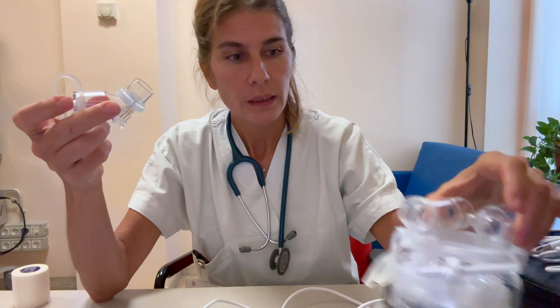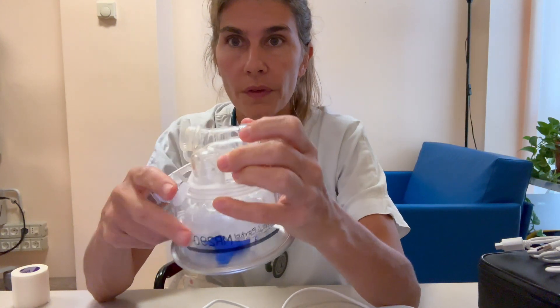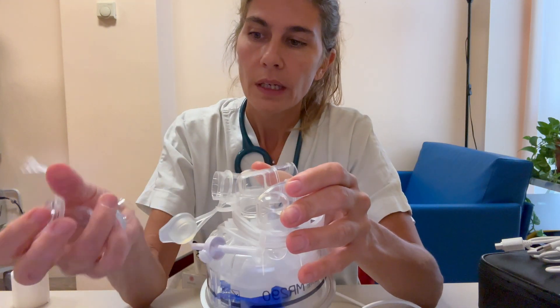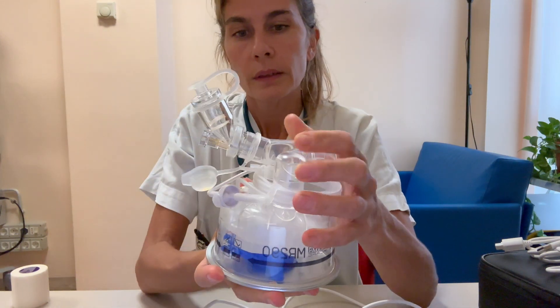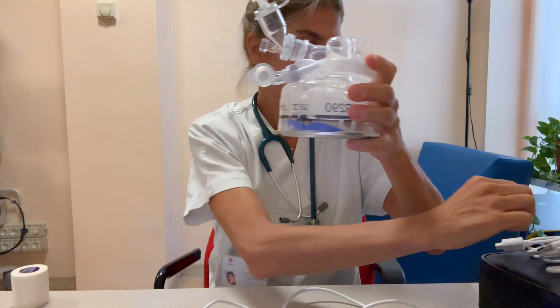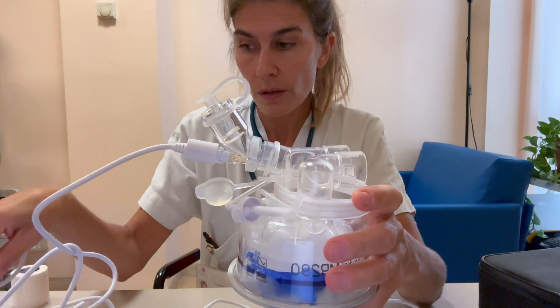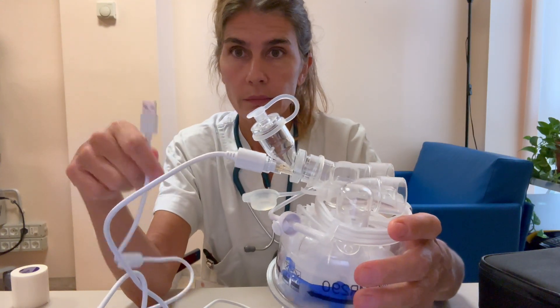On the other hand, when doing high-flow therapy, it's even more simple. This is the dedicated connector for the high-flow therapy device. I connect the medication cap into this hole, and then the cable — this cable is a simple cable since we are not using the flow sensor. These two connect to the intelligent control, and that's it.